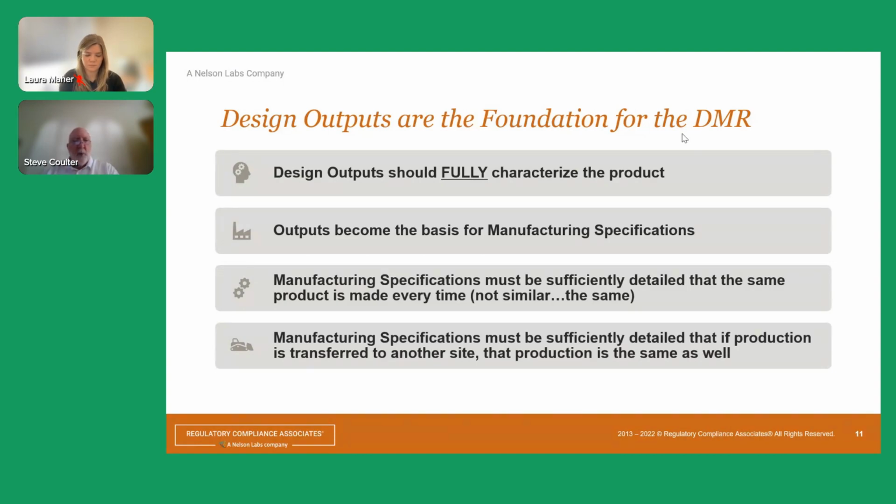The design output is after you have frozen your design. So this is your final design. You've picked your final one. If you want multiple options, then you're going to do a design output for each one of those. That's a waste of time and money for the organizations. So at this point, you should be freezing your options, take your frozen design, and that's the one we're going to characterize.